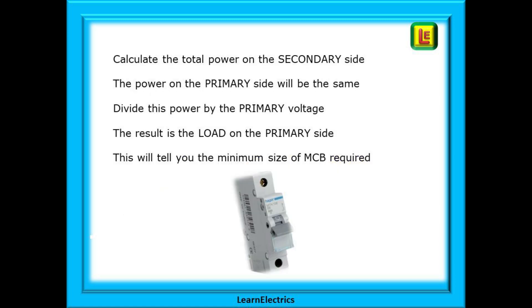And lastly, we showed that if we can calculate the total power on the secondary side, the power on the primary side will be the same. Now, divide this power by the primary voltage, and the result is the load on the primary side. And this will tell you the minimum size of MCB required. And that is all there is to it.